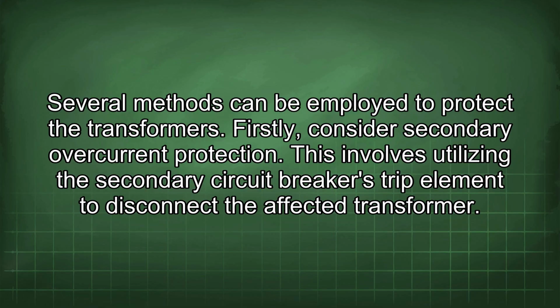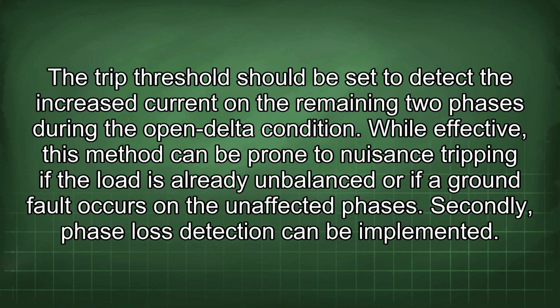This involves utilizing the secondary circuit breaker's trip element to disconnect the affected transformer. The trip threshold should be set to detect the increased current on the remaining two phases during the open delta condition. While effective, this method can be prone to nuisance tripping if the load is already unbalanced or if a ground fault occurs on the unaffected phases.